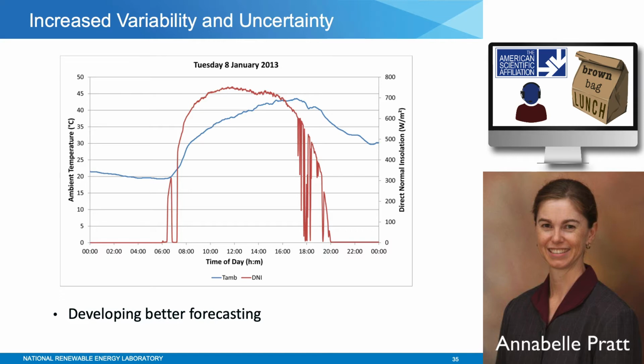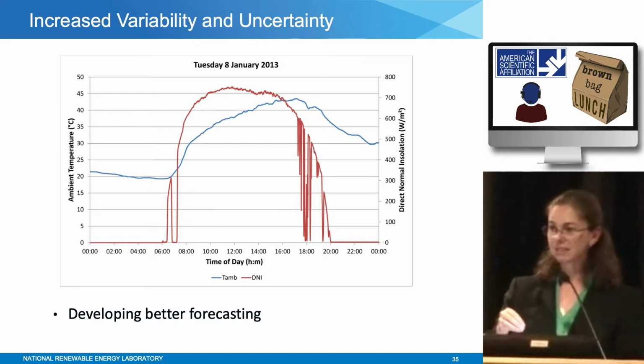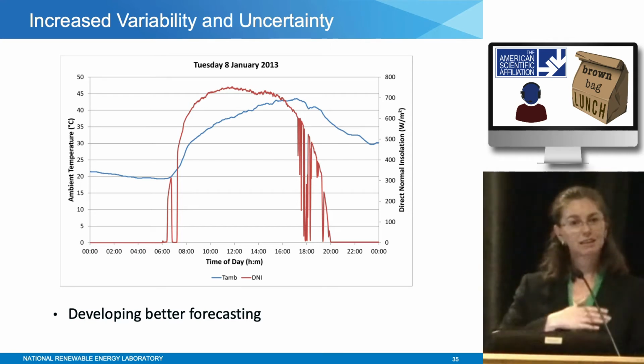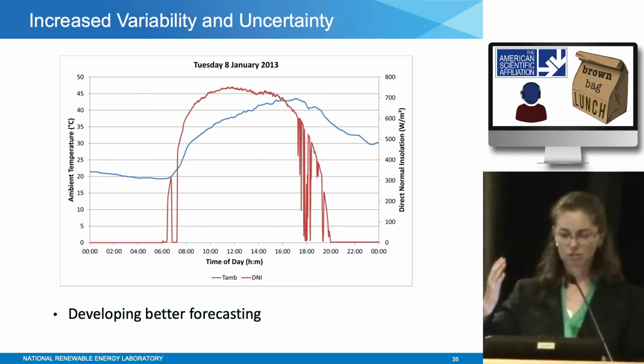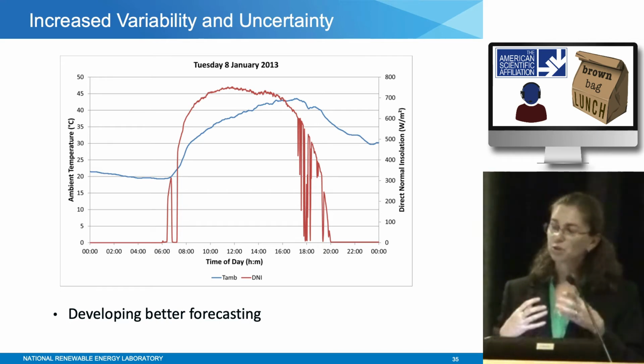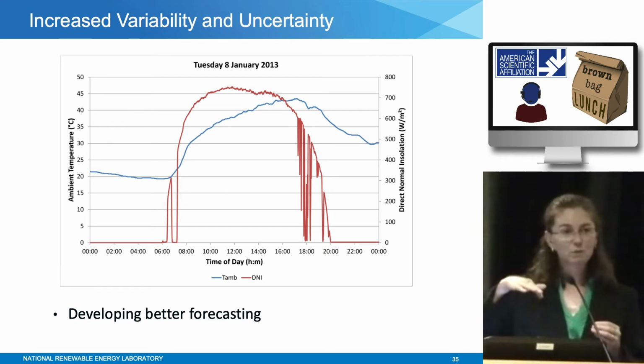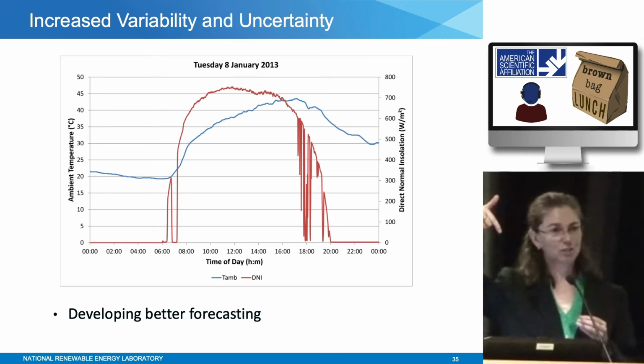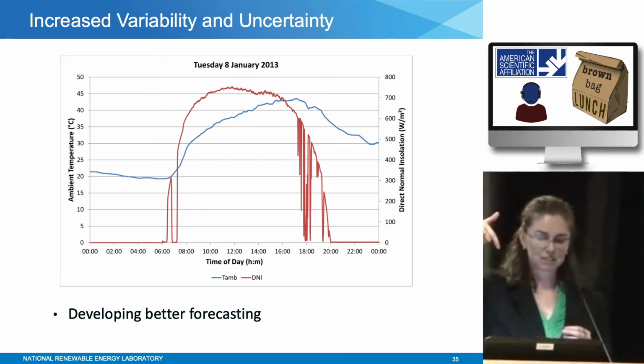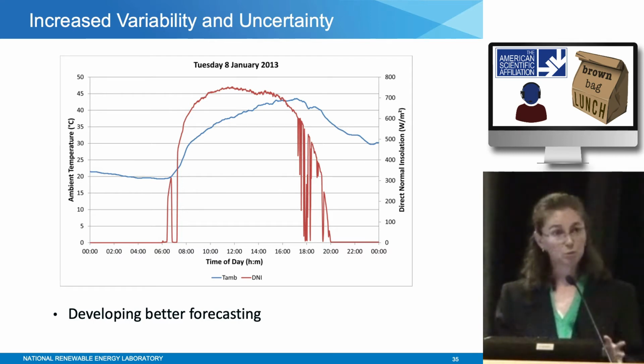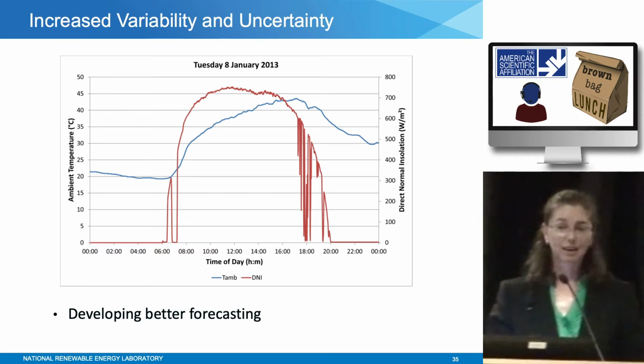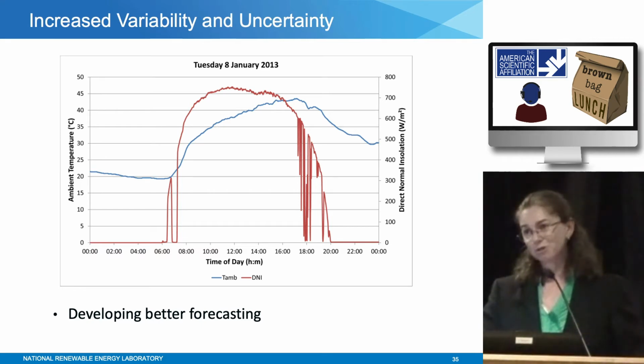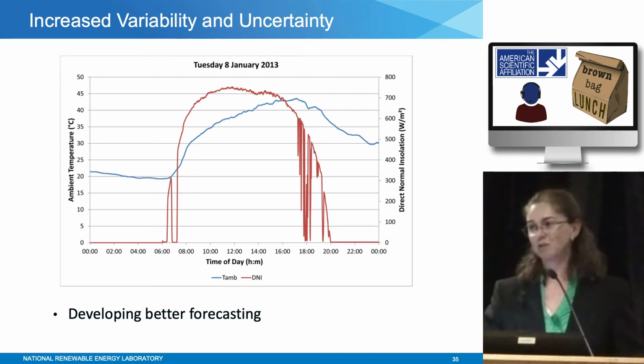You're subject to the weather patterns of that time. This example shows insolation in red, and you can see in the late afternoon a cloud passing over causes tremendous changes in power output. The grid has to be able to absorb that, because when PV drops, another generator has to come online to make up the difference. This is one of the biggest challenges with operating the grid at high renewable penetration, and one of our best tools to combat it is better forecasting—if we can better forecast, we can better schedule conventional generation to make up that difference.